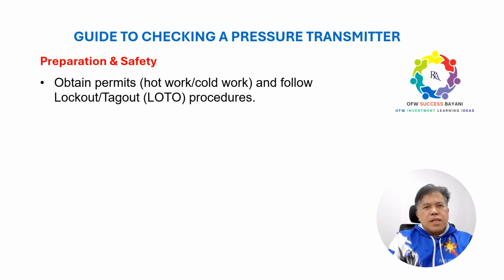So obtain a permit, hot work or either cold work, and follow the lock-out system. If it is brownfield activities for your installation of the transmitter, this is the requirement. LOTO system, okay, that we need to follow. But in the greenfield, of course, there's nothing live at all at the time. So you install, etc., as part of the construction activities. Install, and then that's the time we offer for pre-commissioning, and that's the time we need to be careful with all of our activities. Okay.